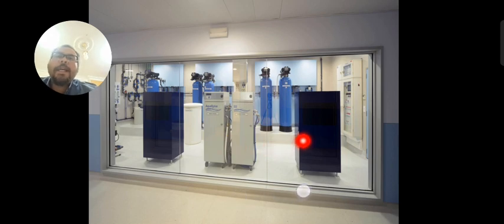Also observe the sterilization and cleaning of this water treatment unit. We must consider that the water treatment units produce a product that goes intravenously into the patient, so it must be completely sterilized and highly pure water.